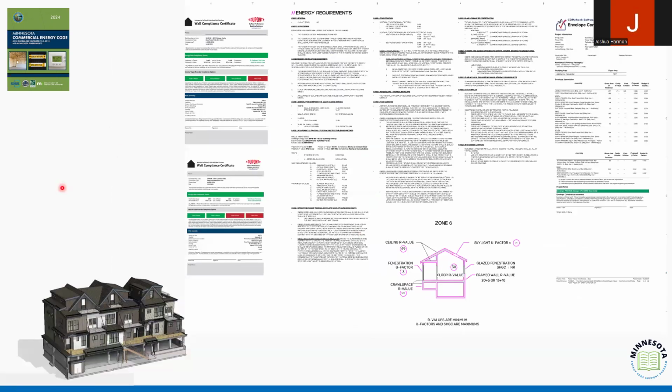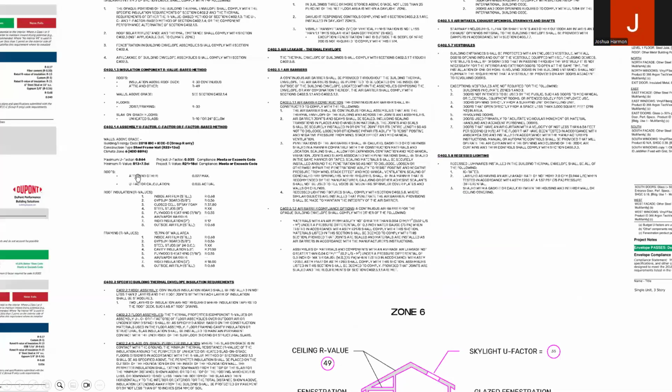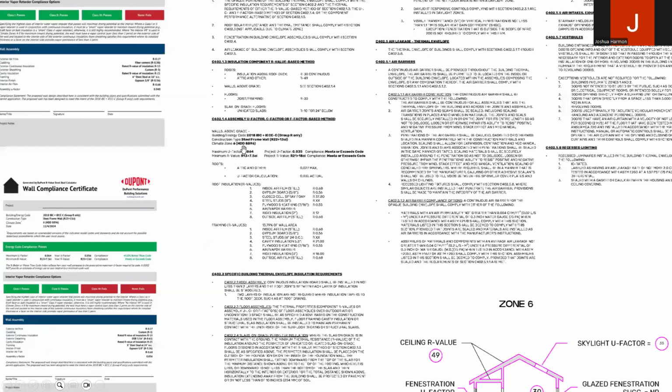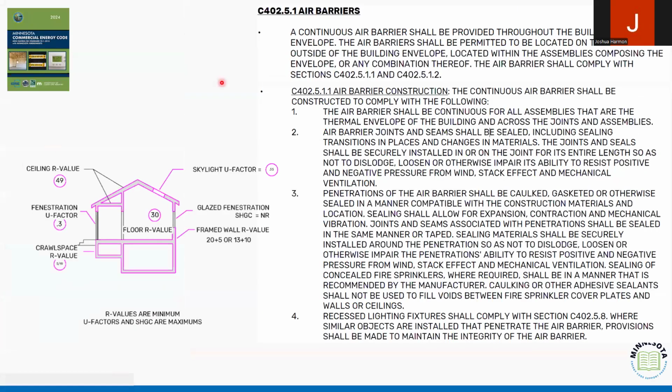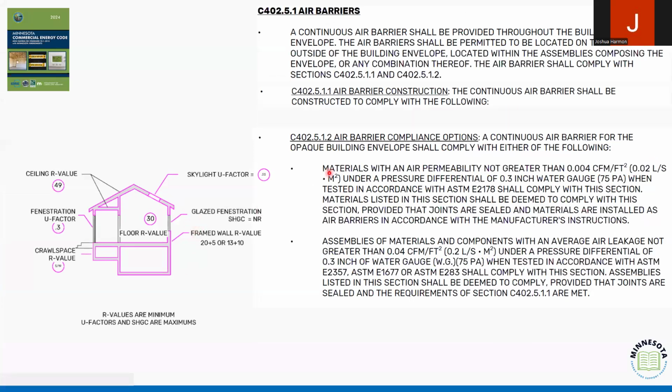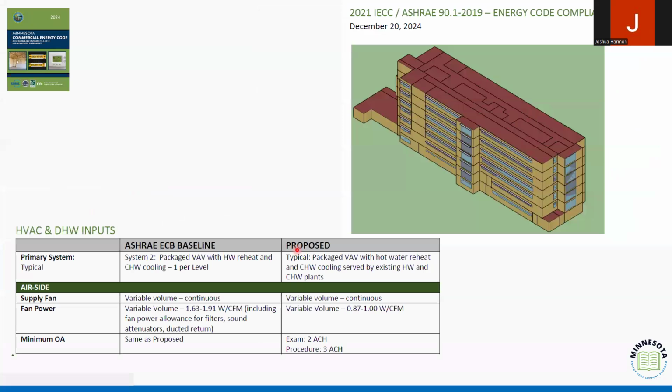And so one of the things that we see, and I'm going to zoom in if I can. Oh, wrong button. And we see it identified again here in that middle section where they've got those walls above grade, and it lists all the components that are going to be a part of that wall design. So that again, I go on site, I'm expecting everything I see here in that building. If I was to keep going, I would see again that they provide all the different instructions for their air barriers, continuity, its testing methods, its expectations, how it's going to perform.